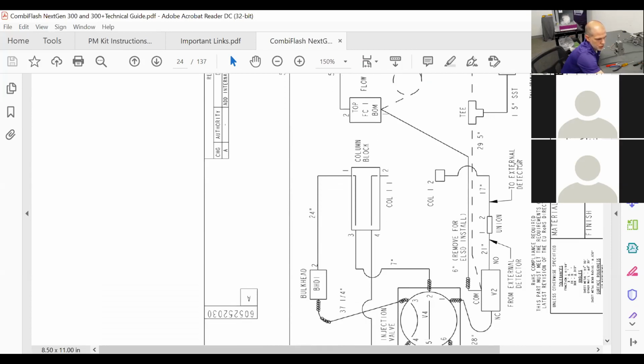To external detector. What that means is that ELSD that we took out earlier. This is a spot where it can attach to. This union isn't always in our units though. As you saw with mine, it connected right up to that three-way valve. The other side went right to that flow cell. So I don't want you hunting for a union that may or may not be there, okay?